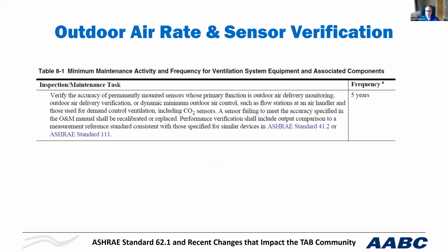Okay, one thing I wanted to highlight here, Section 8 is something called operation and maintenance. And people look at ASHRAE 62 as a design standard, but it really is an evergreen standard. It's going to be everlasting. So a building should be designed to it, it should be built to it, and it should be operated to it. Otherwise, you're not going to maintain the minimum flow rates or the indoor air quality that it sets forth to achieve. So this particular task that I've highlighted here is an important one, where it's talking about maintaining airflow sensors, anything that had to do with operation of the outside air.